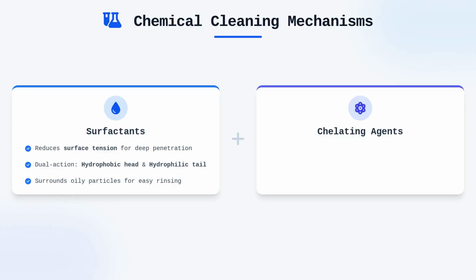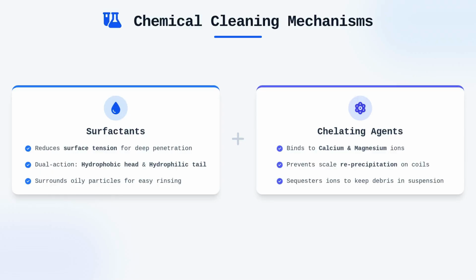Chelating agents, on the other hand, perform a more complex chemical task by binding to metal ions like calcium and magnesium, which are the main components of scale. By sequestering these ions, chelating agents prevent them from reprecipitating onto the coils, thereby ensuring that the debris remains in suspension throughout the cleaning process. This combined action ensures that the coil surface is not just visually clean, but chemically stripped of its parasitic biofilm and mineral layers.